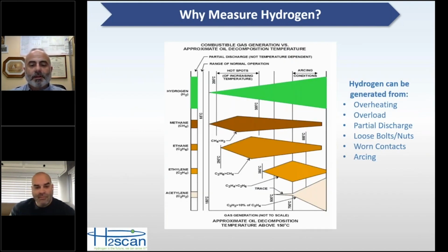Probably most of the people on the call have seen a chart something like this. If you look at hydrogen, it's not generally produced at very low temperatures in the transformer, so you're probably not going to see hydrogen if you're even getting up to around 80 or 100 degrees C. Typically, hydrogen is going to be generated in mineral oil, at least, starting around 150 degrees C, which is hot for you and me, but not super hot inside a transformer. And as the temperature increases, you generate hydrogen at a faster and faster rate.